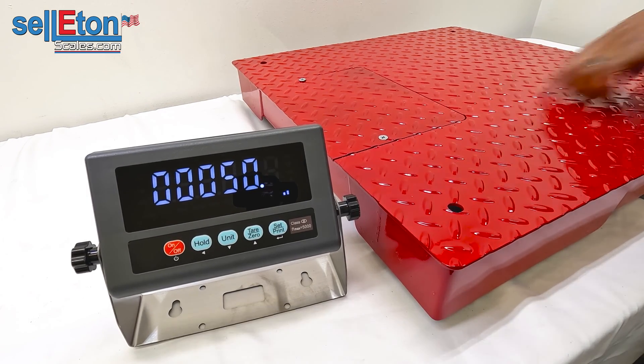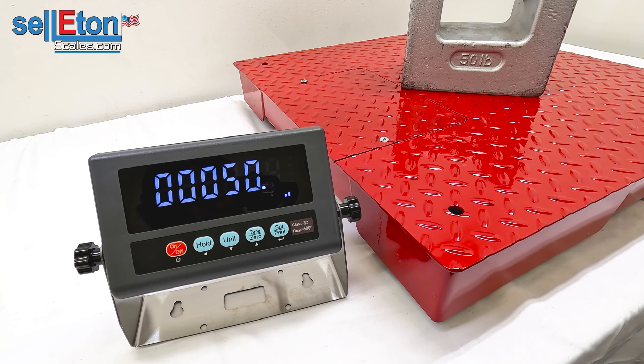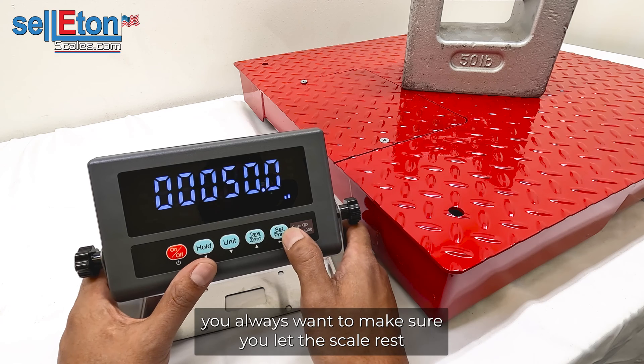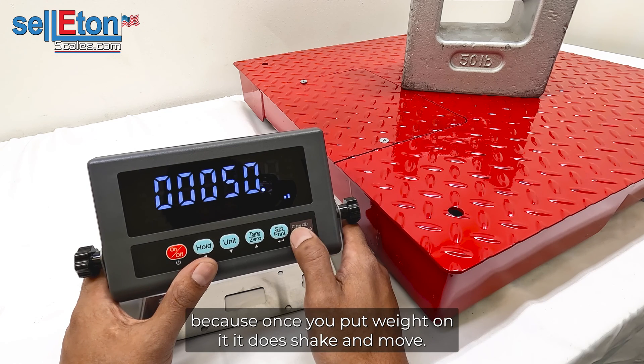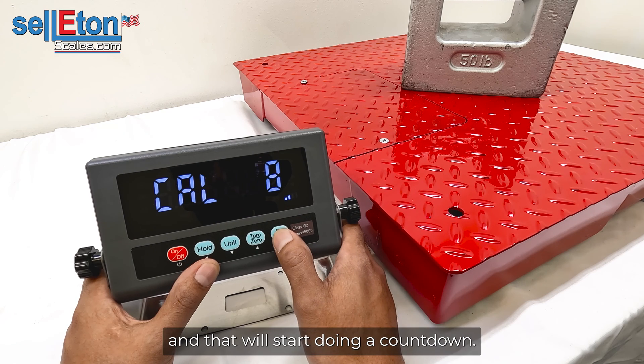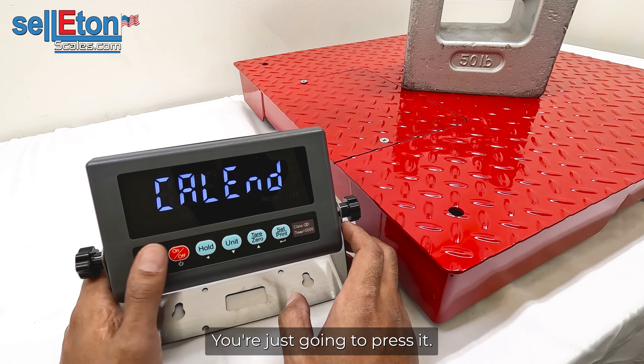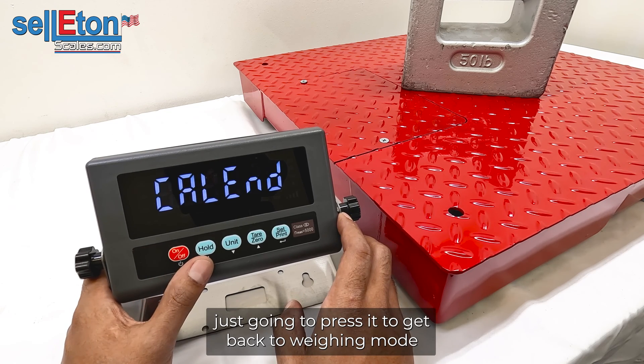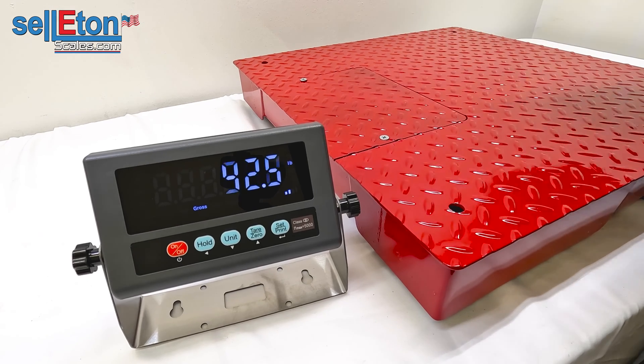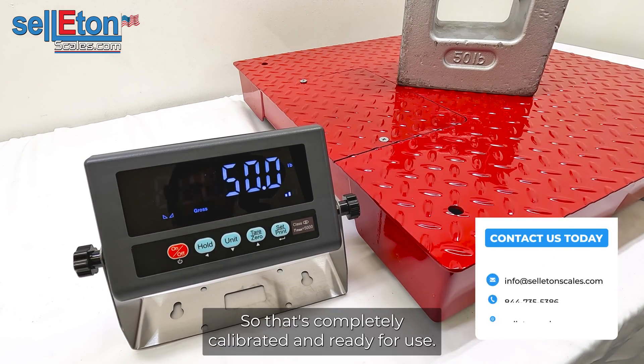Go ahead and place 50 pounds on the center of the scale. You generally want at least 10% of capacity, but this is just for demonstration. Once the weight is on the scale, let it rest so it stops moving. Then press SET and PRINT and it will start a countdown. Once the countdown is done it will show an internal reading, then display 'CalEnd.' At that point press ON/OFF — just press it, don't hold it — to return to weighing mode. The display should show the weight on the scale. You can verify by removing the weight, watching it go to zero, then placing it back — it should read 50 pounds. The scale is now fully calibrated and ready for use.